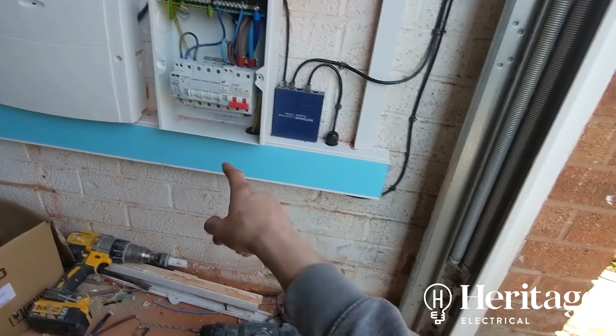Cut into the data cable that comes from the router in the house, goes up into the loft space, and you can see I've just routed it in the trunking. I could do that because even though there's twin and earth run in the trunking, this is shielded cable, so it's shielded to protect against electromagnetic interference. So I've run that in there, put a little compression gland in, so I can jump back into the trunking to come along when the solar goes in.